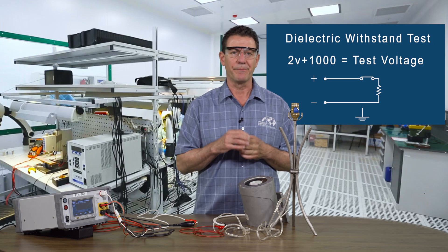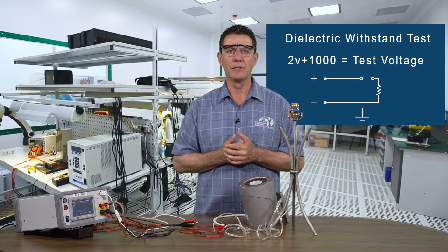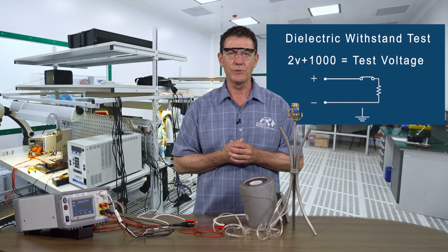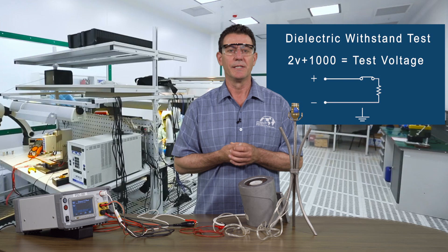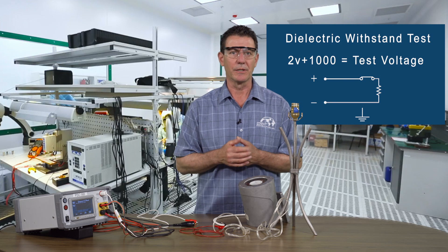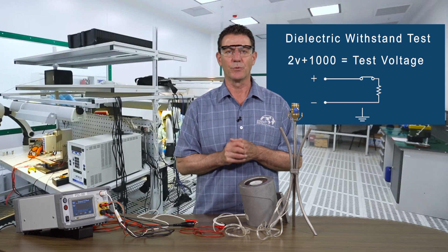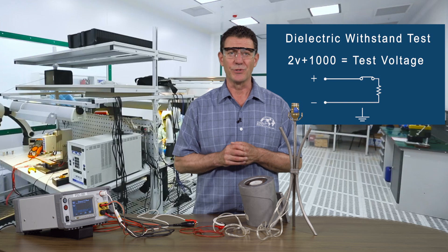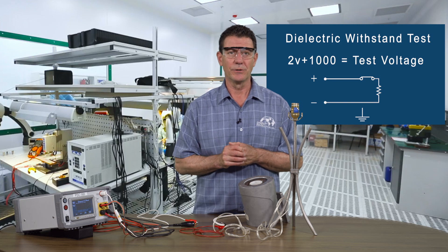Most standards require the test be done at two times rated input voltage plus a thousand volts. Today's purposes we are going to call our input voltage 120 volts so our test voltage is going to be 1240 volts.